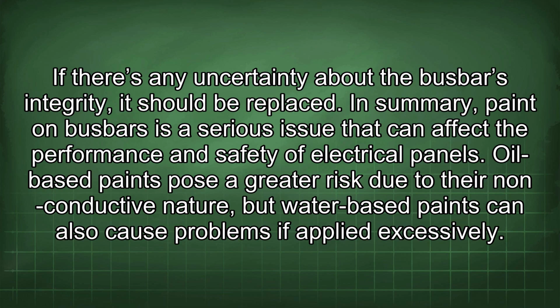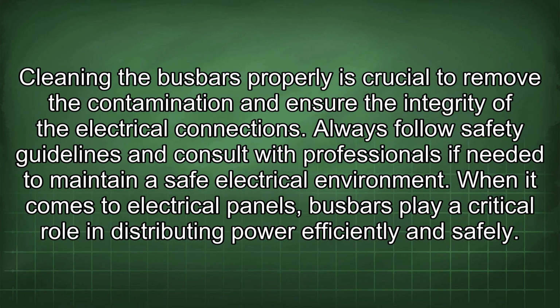In summary, paint on busbars is a serious issue that can affect the performance and safety of electrical panels. Oil-based paints pose a greater risk due to their non-conductive nature, but water-based paints can also cause problems if applied excessively. Cleaning the busbars properly is crucial to remove the contamination and ensure the integrity of the electrical connections. Always follow safety guidelines and consult with professionals if needed to maintain a safe electrical environment.